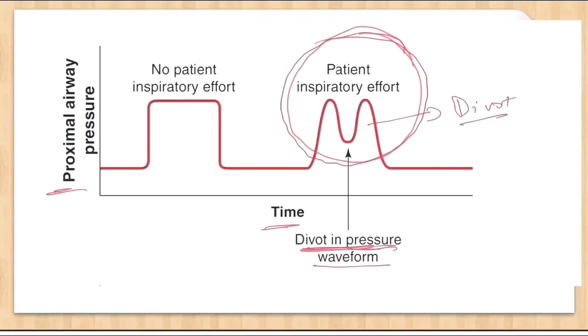Now it is important to note that the patient, despite making inspiratory efforts that reduce airway pressure, cannot trigger the ventilator during the inspiratory phase. I am repeating it. The ventilator does not trigger the breath during the inspiratory phase. If the patient has inspiratory efforts during the inspiratory phase, it is not going to trigger the ventilator. The patient can only trigger the ventilator during the expiratory phase, that is the baseline. So remember, if you want to make sure the basics of the ventilator are clear to you, that the ventilator never triggers in the inspiratory phase. It will only trigger in the expiratory phase.